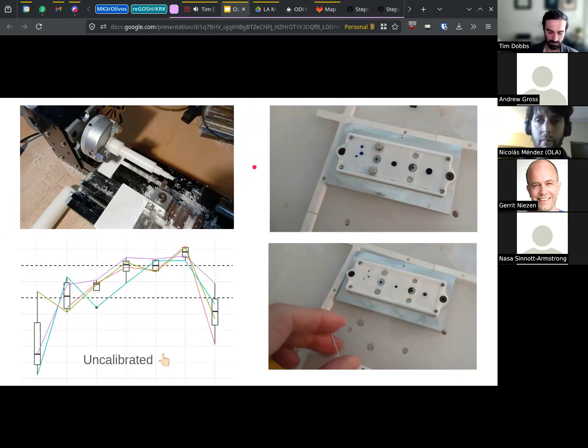One question: you have a really broad volume capacity for this pipette. Is the calibration primarily problematic in the low volume range, or is it equally that you have to calibrate at all volume ranges? Yeah, so this prototype device has 3 volume ranges. The slots here are different depth. This is for the microliter range. This is for the, I don't know, 20 microliter range, and this for the 200 or a bit more microliter range. You can imagine making these larger, and you can squish the drops more in a larger device to be able to quantify the area more accurately.